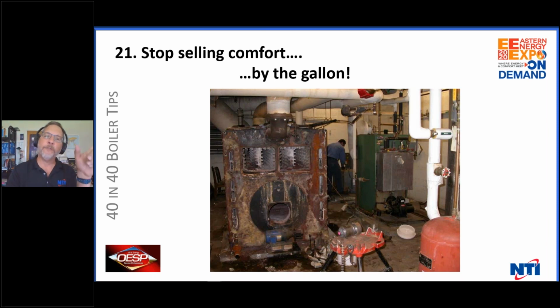Yeah, let's go back to the efficiency ratings that we talked about earlier, right? Stop selling comfort by the gallon. Take heat loads, put in the right size boiler, variable speed boilers or modulating boilers, put an outdoor reset, and gain the trust back in it. Please, you can do it with oil-fired boilers. You can do it with regular cast iron gas boilers. And for God's sake, you can do it very easily using a modulating condensing boiler.